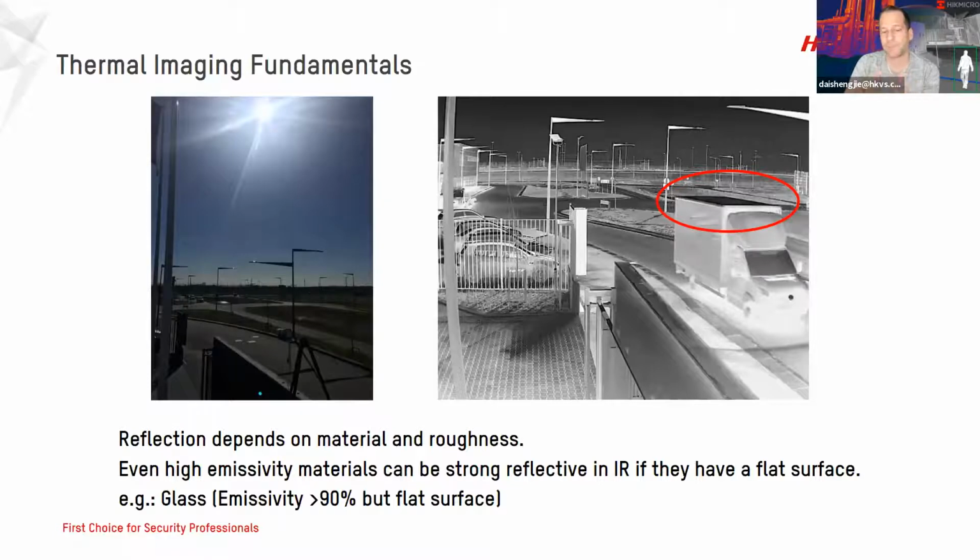It's a cooling truck, so it has this kind of sandwich panels for the box. And he said to me, Marcel, I have a question because I cannot understand the surface. The roof of the box of the truck is for a couple of hours in the direct sunlight, and normally if something is in direct sunlight, it heats up more than, for example, the sides. Why is it so cold and black here in the thermal image?